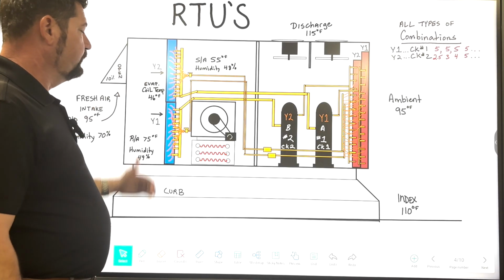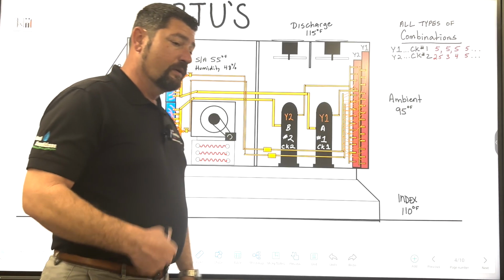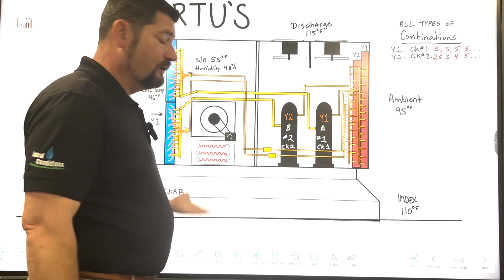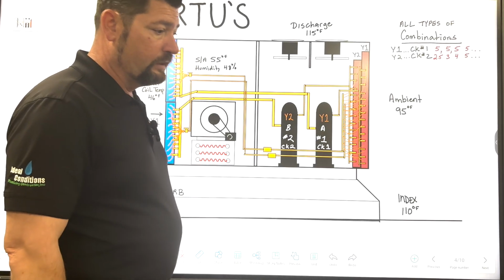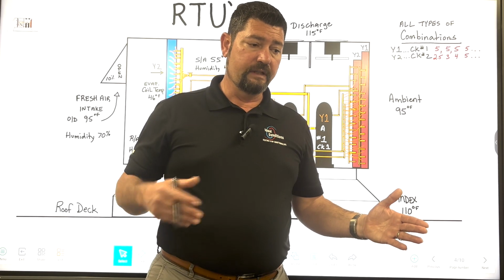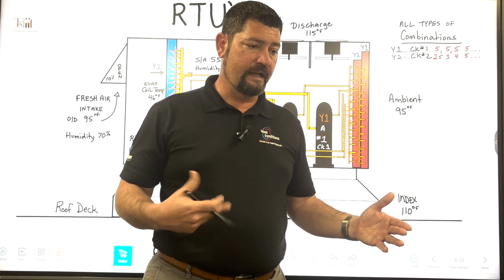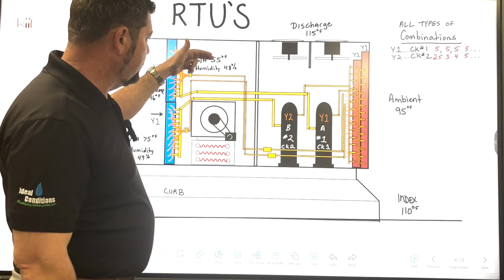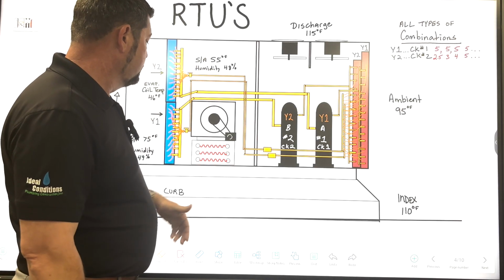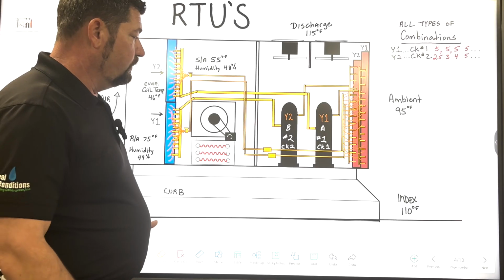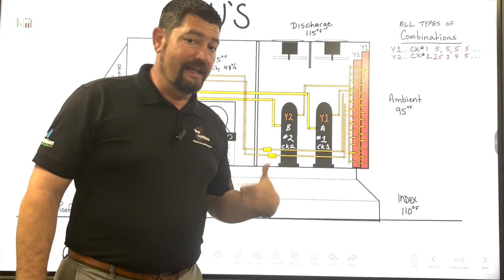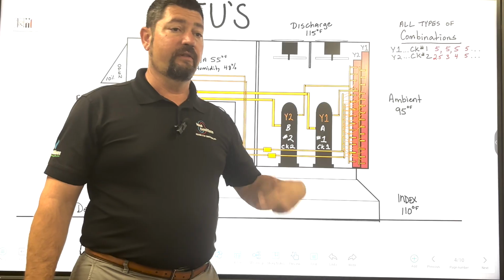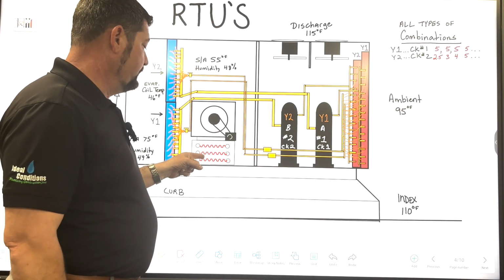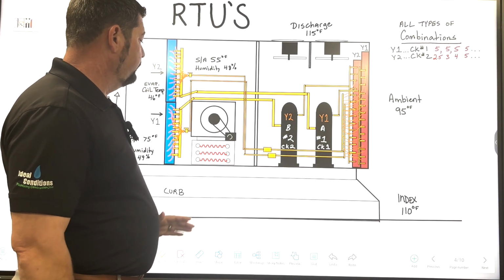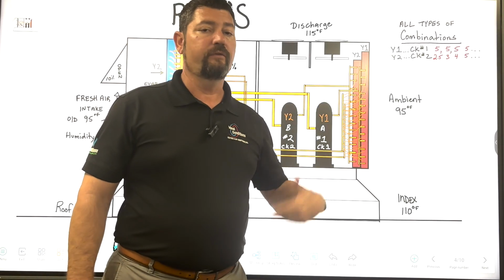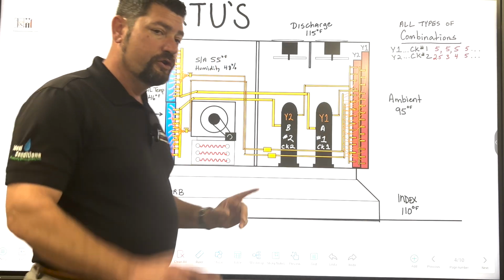If they wanted this to run any lower of humidity, I know you don't want to hear this, may sound a little crazy, and it's going to be very expensive, run the heat strips with it. You're going to create a longer run cycle because you're adding heat to the building, right? And when you add heat, as I cool air down to 55, I'm going to warm it back up to almost 75 degrees. And so now the only thing I am doing is removing moisture. And it's going to run forever. And so the heat strips will dehumidify by themselves. The coil's dehumidifying, plus the length of run time, it never cycling off, will be a third way of dehumidifying. Do not do that.